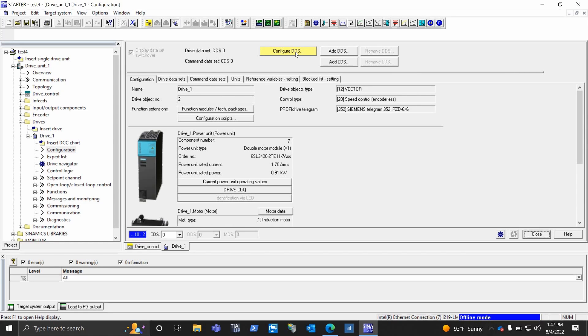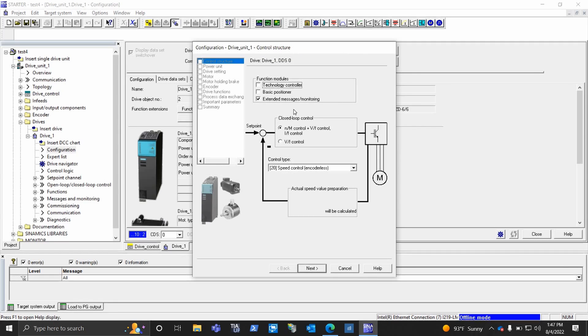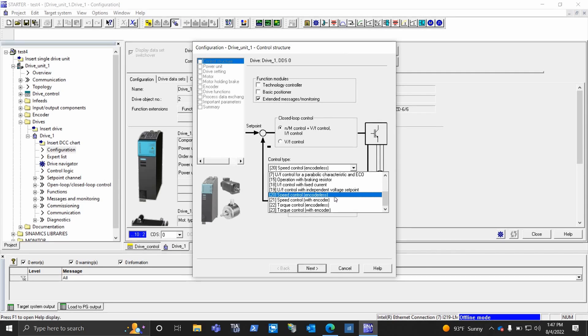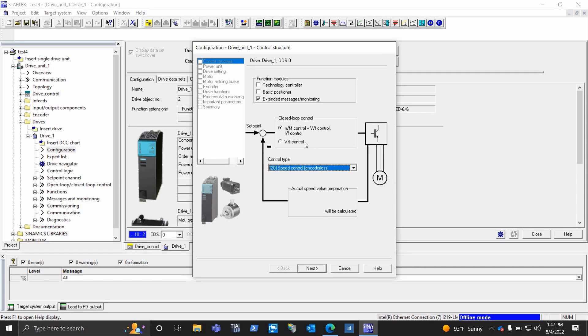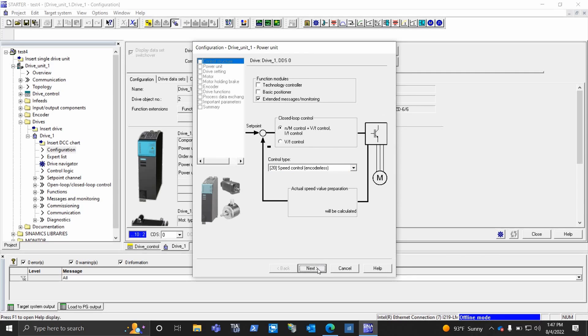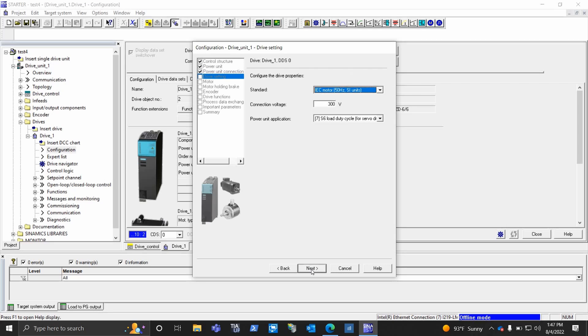Now I'm going to tell that I want to configure. In this case, I'm going to show I want to set this thing up as encoderless, so you change this to whatever you want. In this case, I'm going to show encoderless with speed and vector control. Now these settings are already set for what I have. I have actually a special double axis module, so that's why it's shown as that, but I only have one connector connected, connector one. You'll only see one connector for most drives.